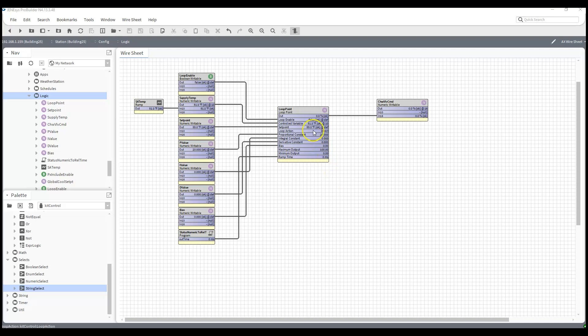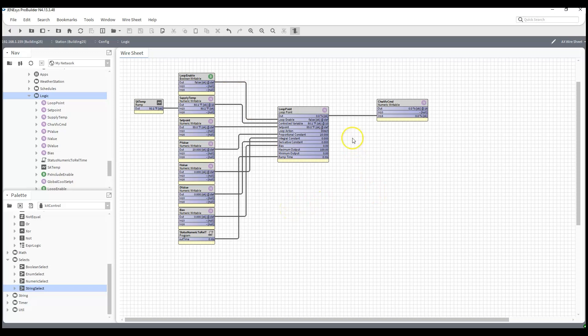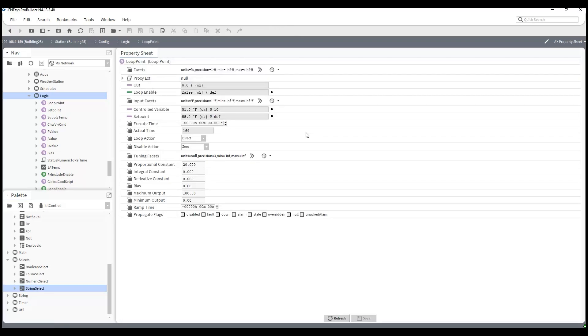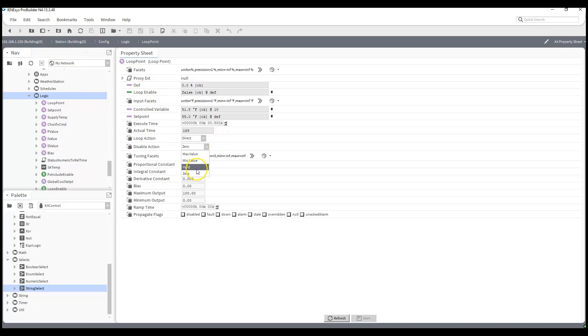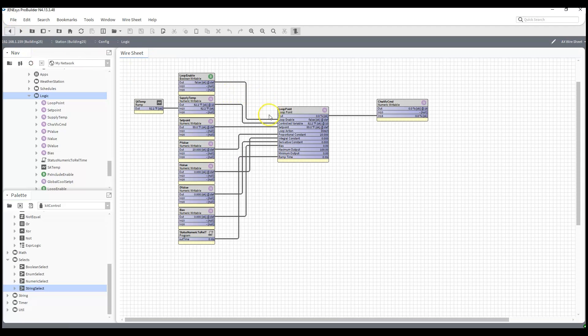We have a few properties. The first one is the loop enable - typically this is going to be some kind of status but could be another way to enable or disable the loop. If the loop is disabled we have several options to control our output: we can go to max value, min value, hold whatever current value we currently have, or go to zero, which is what I actually do. The control variable is your modulating input, whether it's temperature, flow, pressure, something that is continuously changing. And the set point is what we're actually trying to control our control variable to.